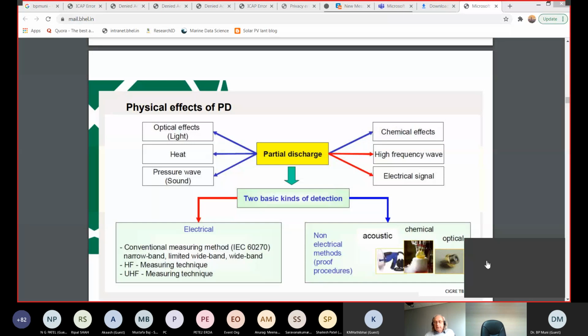For example, if you have a gas insulated substation, then it's quite easy. Gas can exchange itself quite easily over time, and the discharge is in an inhomogeneous field, so you can accept a little bit higher PD levels, like 5 or 10 picocoulomb. If it's polyethylene and you have a defect inside the polyethylene insulation, and you can pick it up, 1 picocoulomb could be definitely dangerous and will kill your cable in 1 hour, 2 hours, whatever.